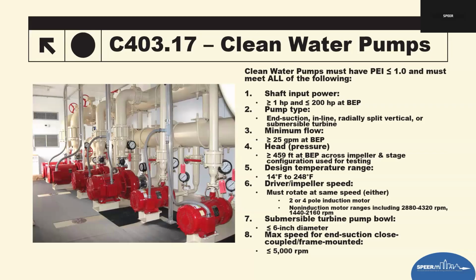Motor compatibility: the pump must be paired with a motor that runs at the same rotational speed. This can be a standard 2-pole or 4-pole induction motor or specific non-induction motors that operate in a range of basically 2,800 to 4,300 RPM or 1,400 to 2,100 RPM. This ensures the pump is tested and operated under a standardized condition of speed.